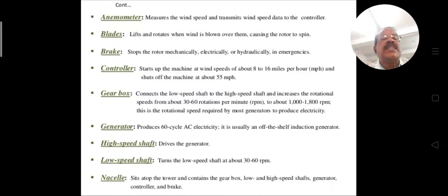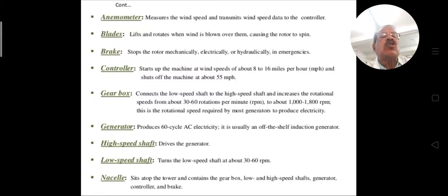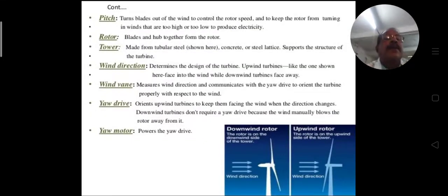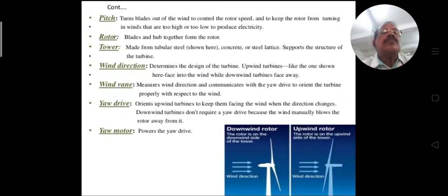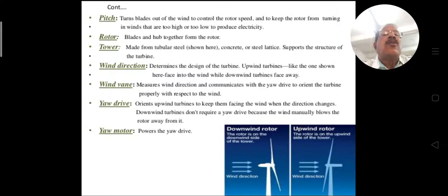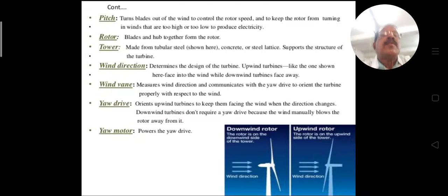The nacelle sits atop the tower and contains the gearbox, low and high speed shafts, generator, controller, and brake — this total unit is known as the nacelle. The pitch system turns the blades out of the wind to control the rotor speed and to keep the rotor from spinning when winds are too high or too low to produce electricity.